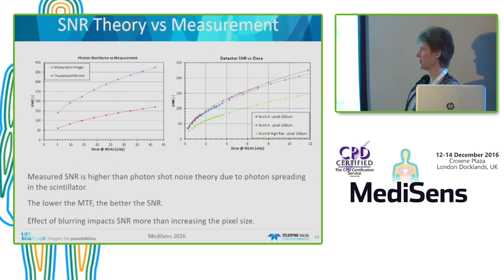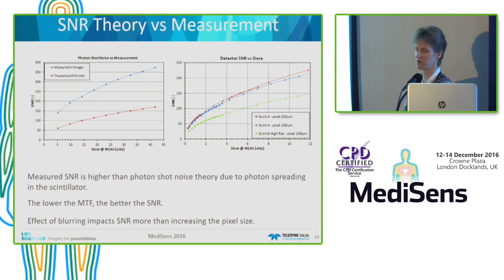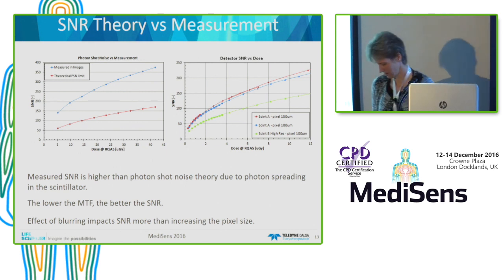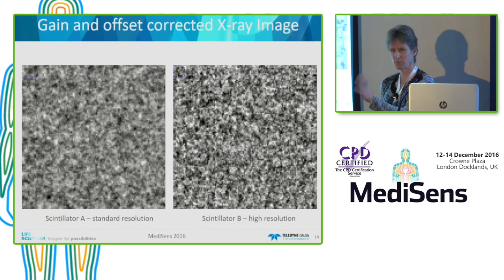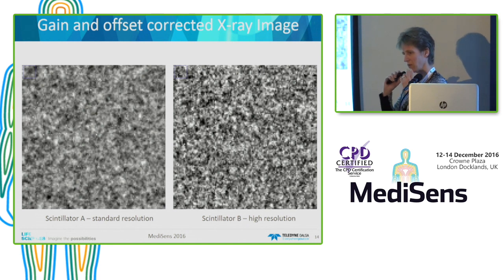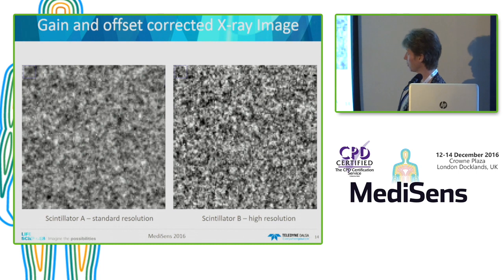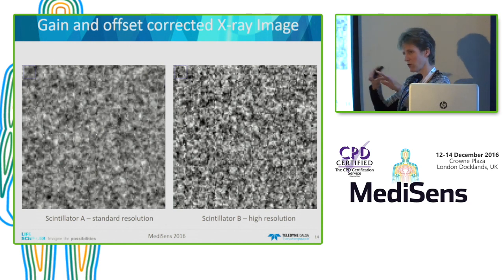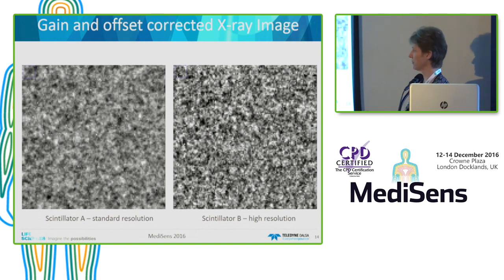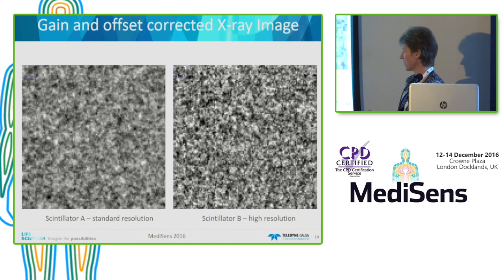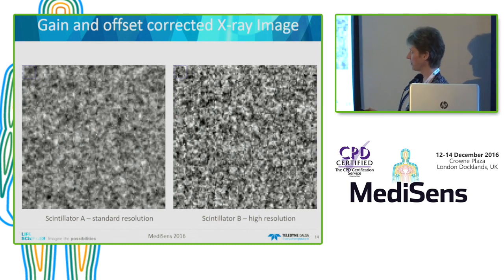So if you make a detector with a very bad MTF performance, you will achieve a very good signal-to-noise ratio. This image shows how you see this in practice. With an evenly illuminated x-ray image and equal contrast enhancement applied, this is the difference in noise you observe: the standard resolution detector image looks much more gradual, while the high resolution detector image is much noisier. Actually, the high resolution image better represents the noise present in the original signal. Interestingly, clinicians don't like this — they see it as a noisy image and prefer the smoother-looking images, expecting to see much better contrast in those.